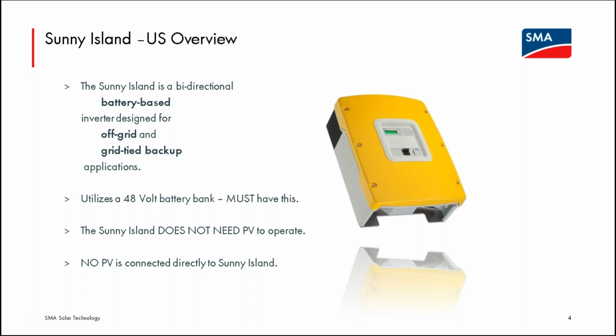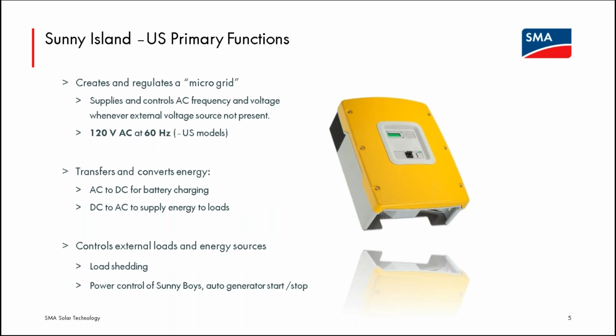So it is a battery inverter only. It obviously can take power from the battery to create an AC microgrid. So it can go from DC to AC, but it can also take AC power, charge the batteries via DC, so it can convert AC back to DC. So it's a bidirectional battery inverter. The Sunny Island US models, each device creates a 120 volt, 60 hertz waveform. We'll talk about clusters of islands where you can create a 3-phase grid or a split phase grid, but each device individually will create a 120 volt, 60 hertz waveform.